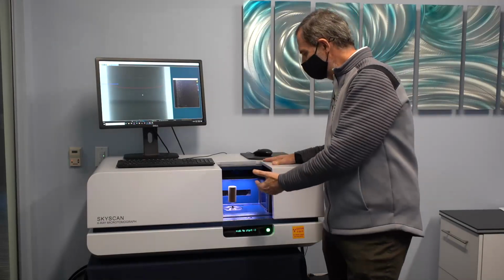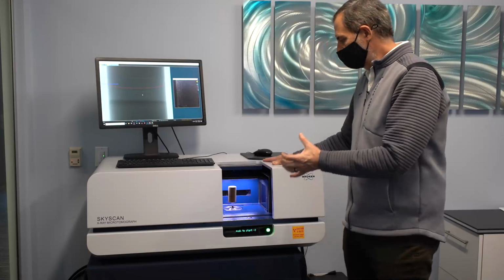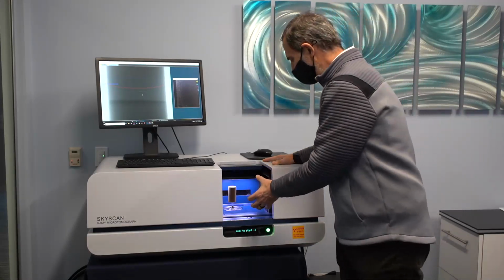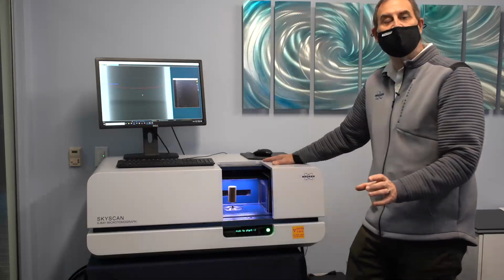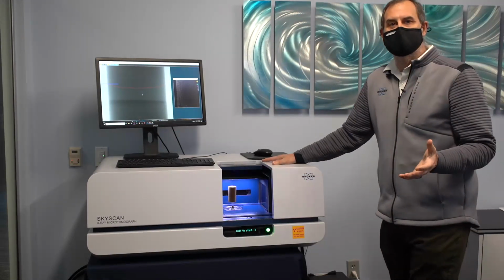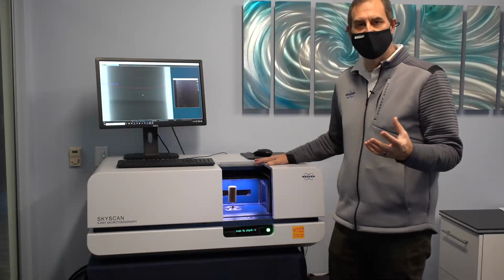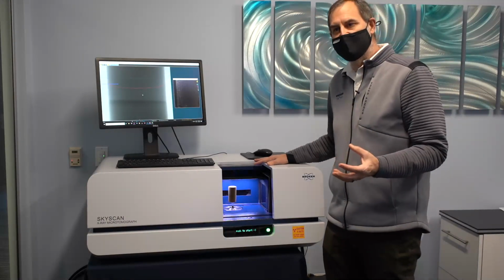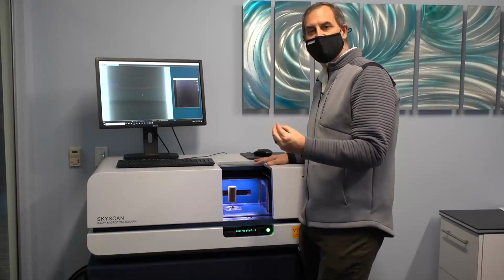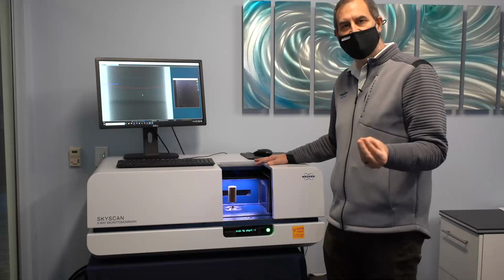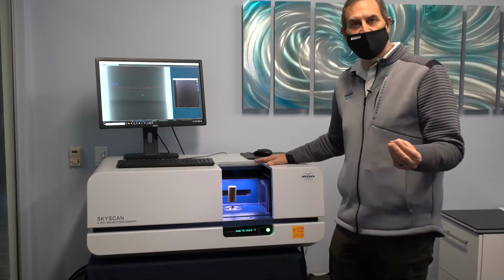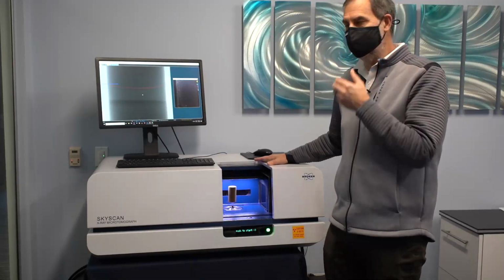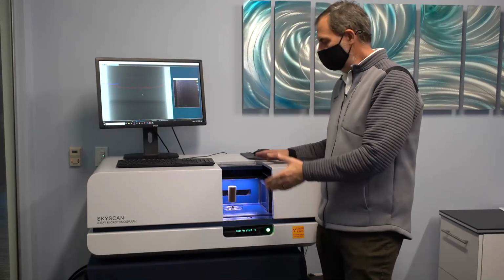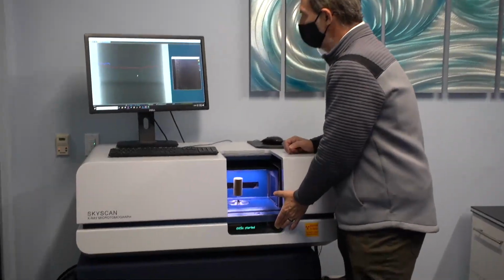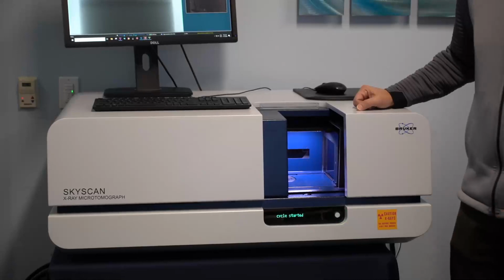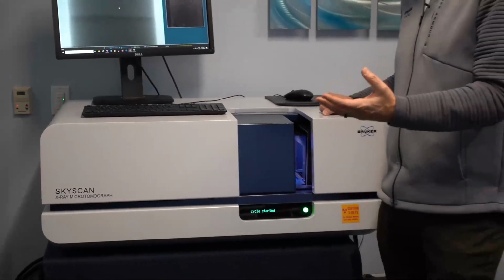This system also has features like spiral scanning and a large sample chamber. This system can handle a sample that's 4 inches by 4 inches. This is my go-to system. I like this system because I always know that I'm going to get good quality, high resolution data. It's easy to set up, it's easy to operate, and has a full set of software features that you can use. But also it can be programmed. So for your daily use, if you're running routine samples, it can be programmed with a push button analysis. So anyone can put their sample on, push the button, and the system will then go and do all the measurement and all the analysis for you.